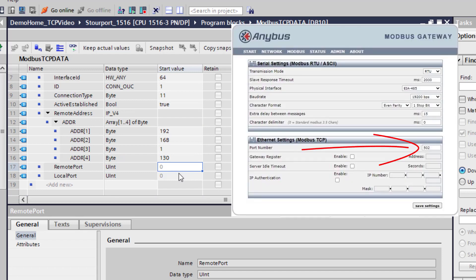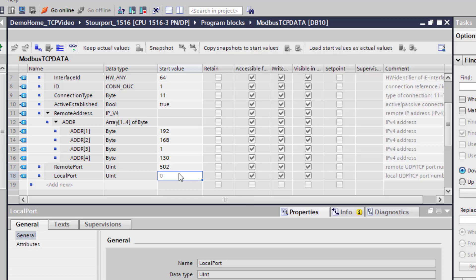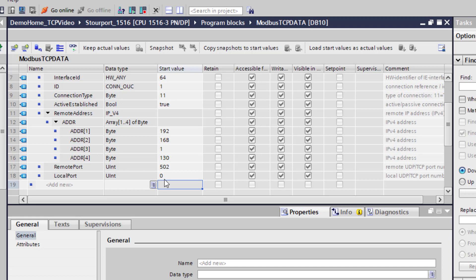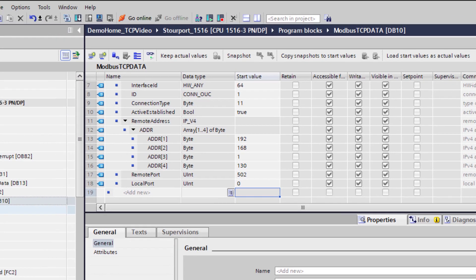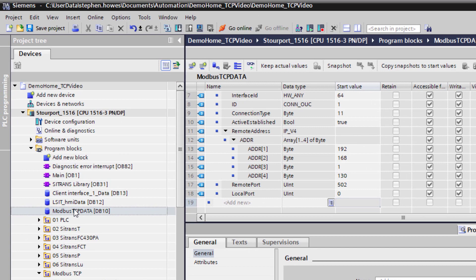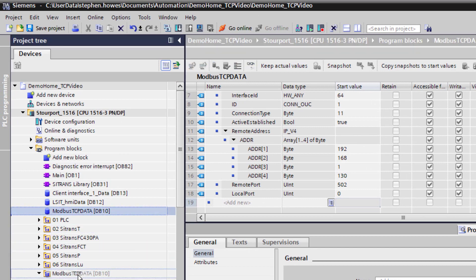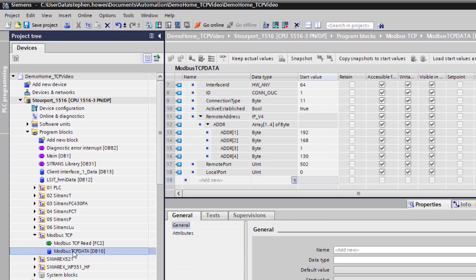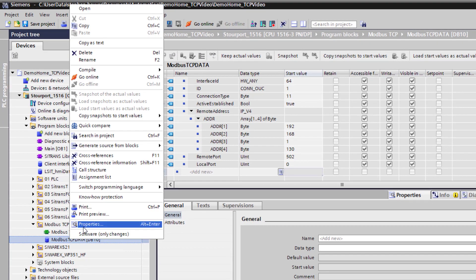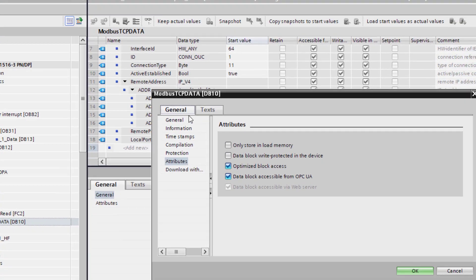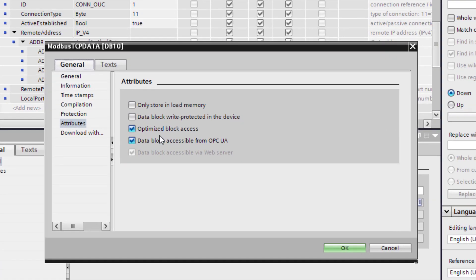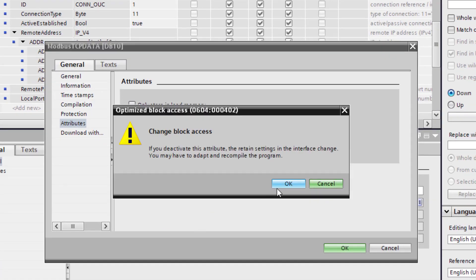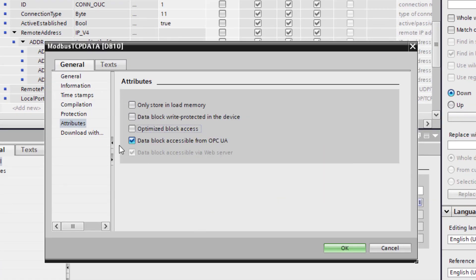And then we have the remote port. So going back to the previous video which you can see the link at the top, we set the port up to the default port for Modbus TCP which is 502. If you leave your local port set to 0 it will just copy that port, but if that one is already being used it will stick it into another port. So once we have got that there is something else that we need to do. First of all lets just tidy that up and put it in the same folder. We need to go to properties and then under attributes, untick optimize the block.